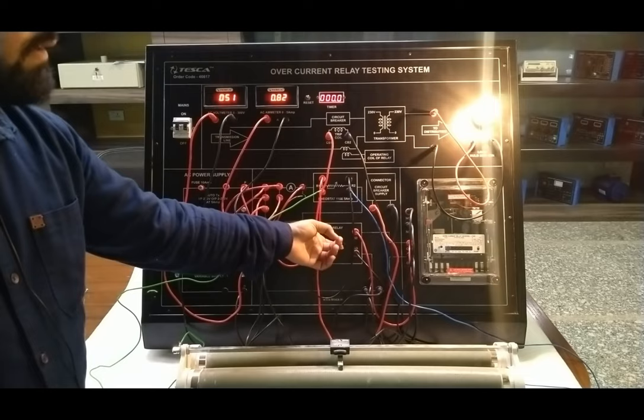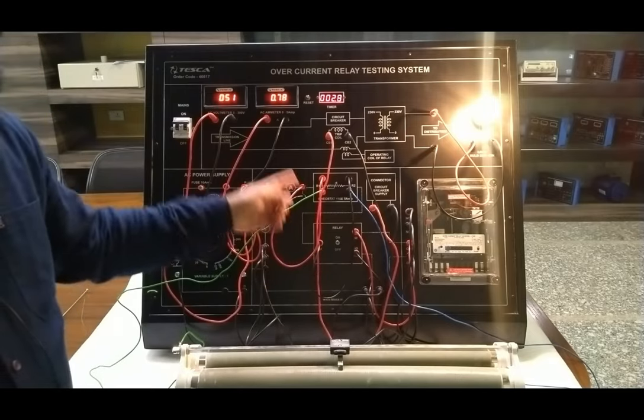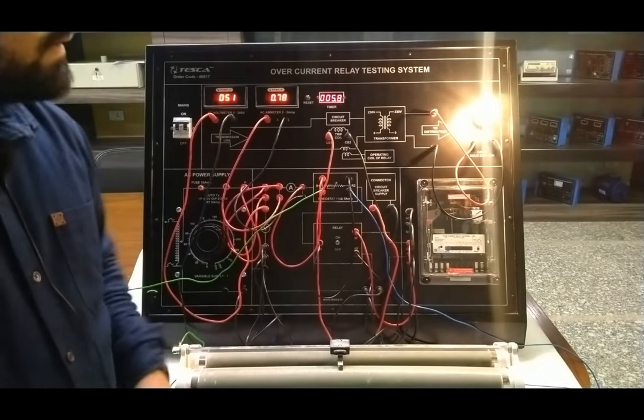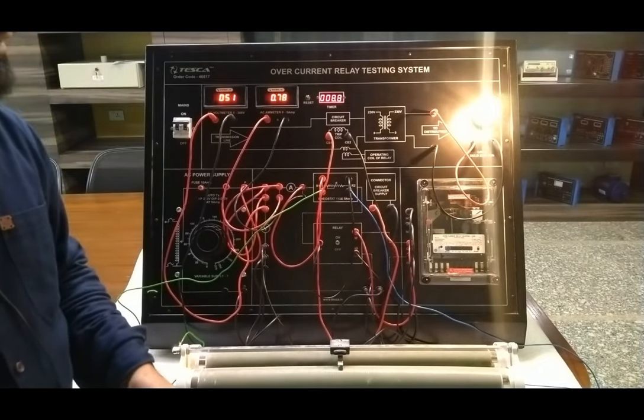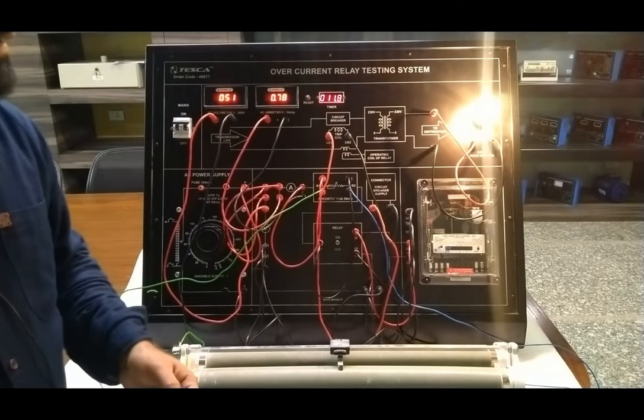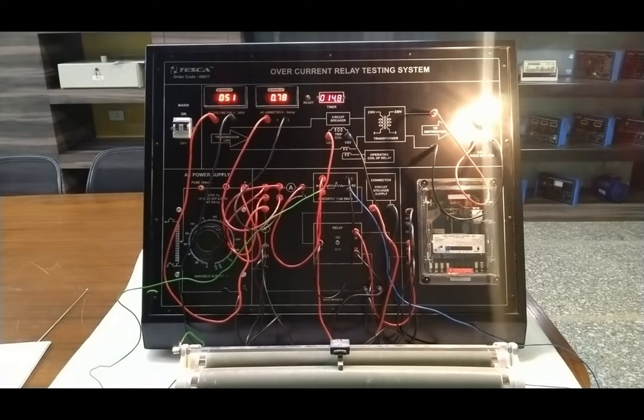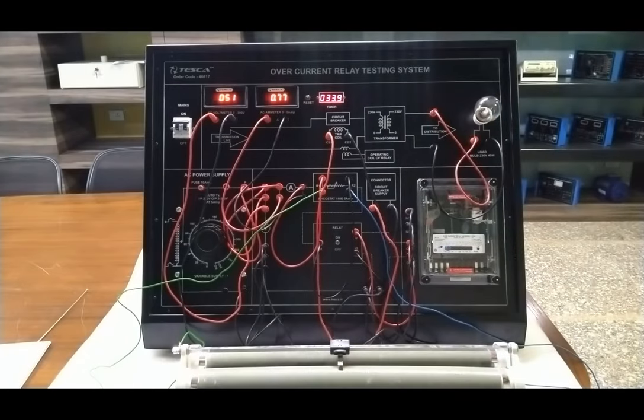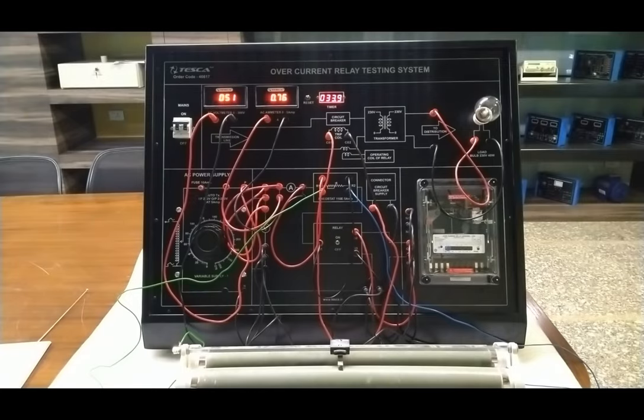We have provided overcurrent beyond the setting value. Now we will turn on the switch and see how much time the relay takes for tripping. As I turn on the relay, the current slightly drops and the relay is energized — it now starts rotating the disc, and the disc will trip the system in some time. The time will also be marked and stopped on the timer, giving us the accurate time for tripping the system.